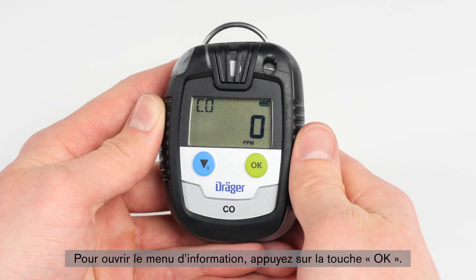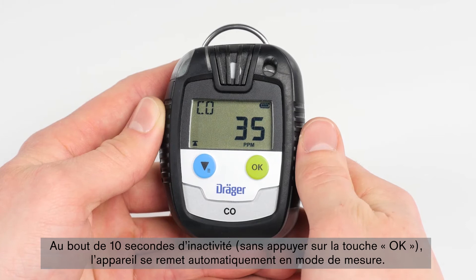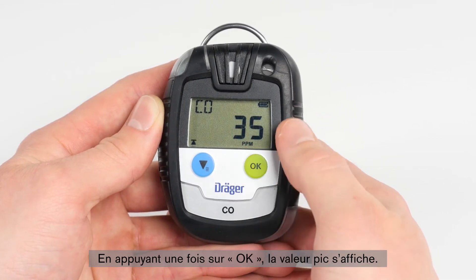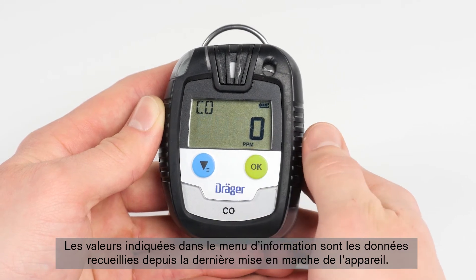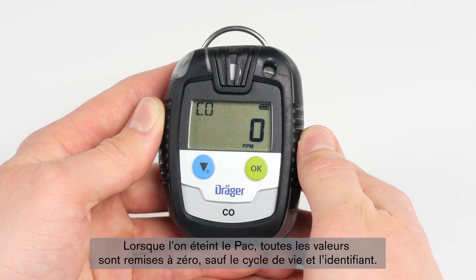In order to open the information menu, press the OK button. Note that after 10 seconds of inactivity, without pressing the OK button again, the device will automatically switch back to the measuring mode. When first pressing the OK button, you will see the peak value. When pressing the OK button again, further information is shown. All values indicated on the information menu refer to the data collected since the last time the device was switched on. When the Pac is switched off, all values will be reset except the lifecycle and the ID.